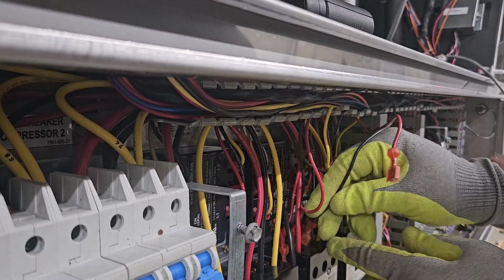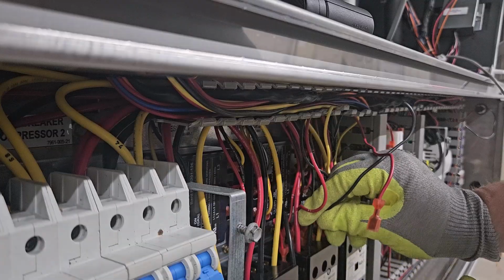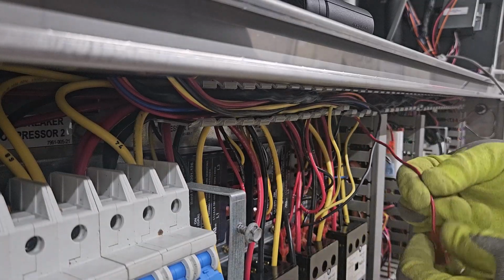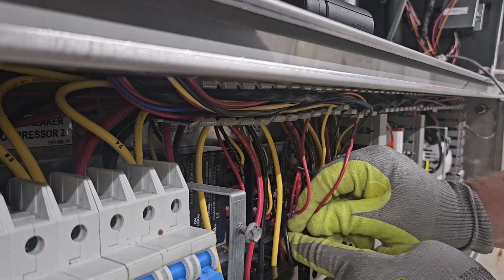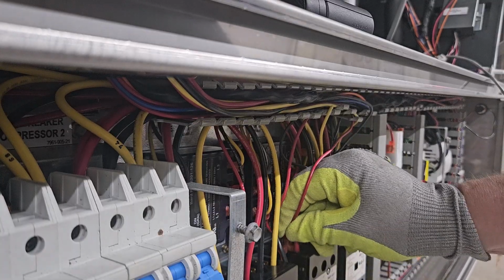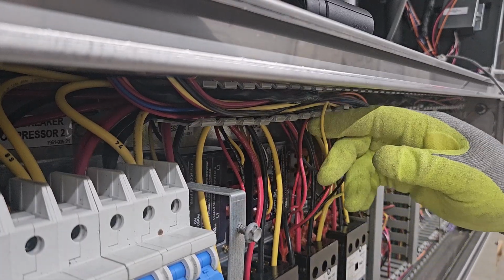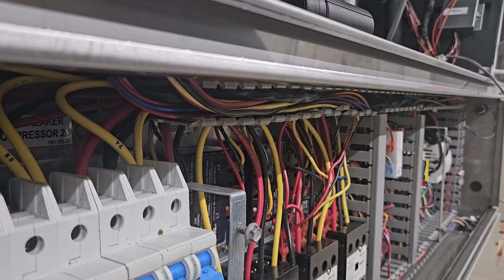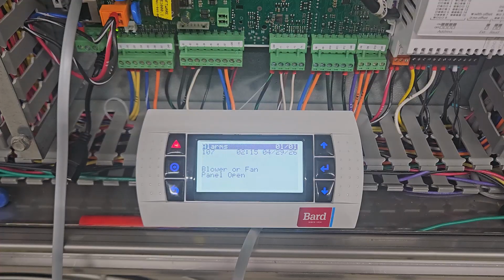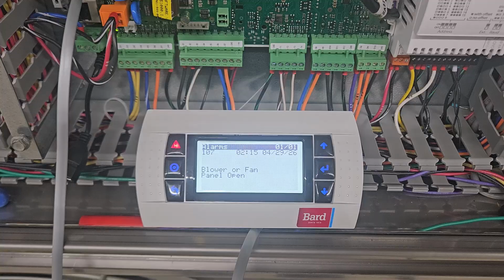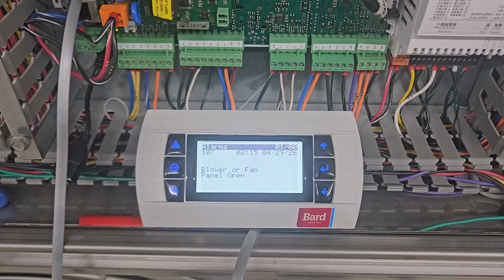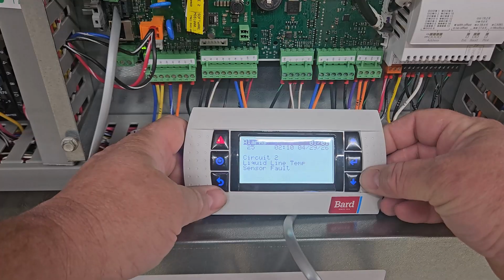They will be connected on the line side of the contactor. The evaporator and the condenser motors are receiving power all the time. Once all high voltage and communication wires have been placed, it's now time to power the unit on. Please note, door panels have switches which prevent operation of the indoor fan motor while they are open, and it may be necessary to install the panel while testing the unit.